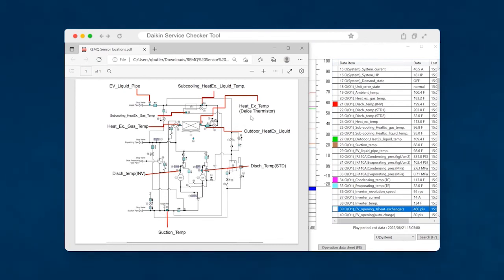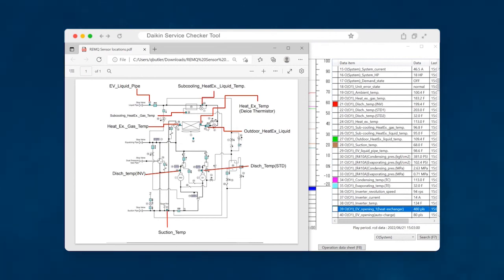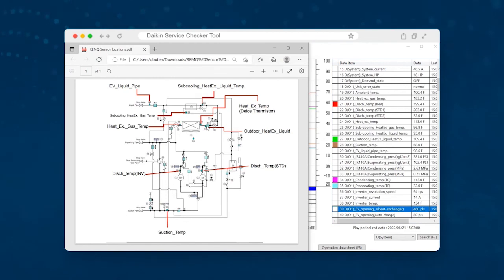Because I mean, it might be something that's similar, but kind of different. So it's easy to get confused, but just keep in mind, if you calculate superheat, just like you calculate superheat on a conventional system, if you calculate subcooling, just like you calculate subcooling on a conventional unit, you want to take your subcooling measurement just immediately out of the heat exchanger, right? So just your liquid pipe, that's all it is before it gets anywhere else. That's where you take your subcooling measurement. Now, this is cooling mode. Heating mode is going to be a little bit different. That could be a whole different video in itself.